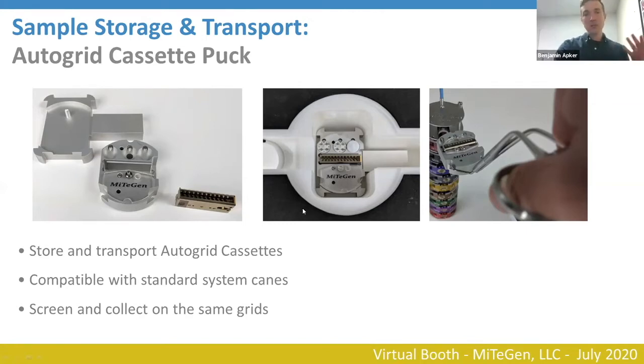The vision is that this will allow users to prepare their clipped grids at their facility, and then if they have a Glacios, screen their grids with an autoloader, and then send the same grids off for data collection at a high power microscope — or to just clip and prepare their grids and send them off for data collection.